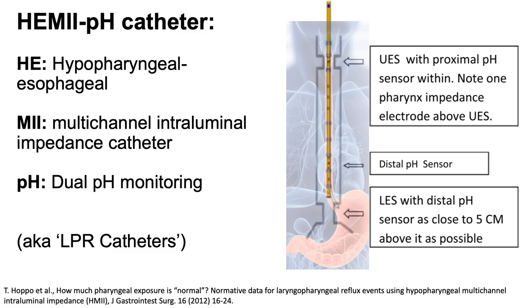Multi-channel intraluminal impedance catheters afford detection of liquid reflux events regardless of pH. The impedance electrode pairs detect presence of a liquid by measuring change in resistance to current flow when interfaced with electrolyte-rich fluid. That is, impedance between the electrodes decreases in the presence of conductive fluid. When multiple electrode pairs are mounted on a single catheter, directionality of the bolus movement can be measured. Thus, we can determine retrograde flow. A specialized impedance and pH catheter is available to better diagnose LPR. These catheters include pharyngeal impedance electrodes to detect liquid escape into the hypopharynx, as well as pH probes and impedance electrodes buried in the upper esophageal sphincter, or the UES, and the proximal esophagus. Thus, it is termed hypopharyngeal-esophageal multi-channel intraluminal impedance testing with dual pH monitoring, abbreviated HEMII-pH catheters or LPR catheters.